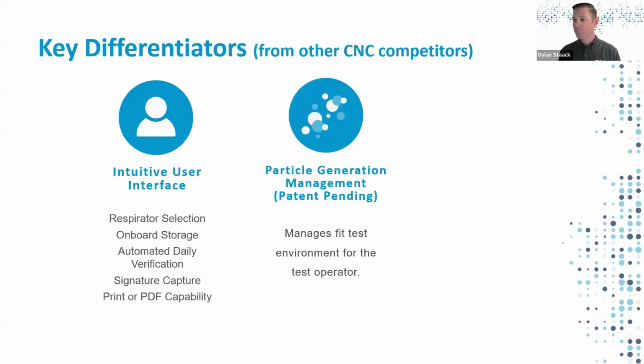right in the test zone of the fit test subject. With particle generation management, we've hooked our particle generator up to our machine, and our generator communicates with our machine. It is designed to turn on and off on a sequence that we've created. We've gone through and tested and made sure that we have the ideal fit test environment at that timing sequence. So at different parts of the fit test it's on, at different parts of the rest cycle it's off. You're not just blowing particles the entire time and flooding the environment, potentially harming your instrument. You're only creating particles when you need them in the fit test and at small intervals in the rest period to help maintain that environment.